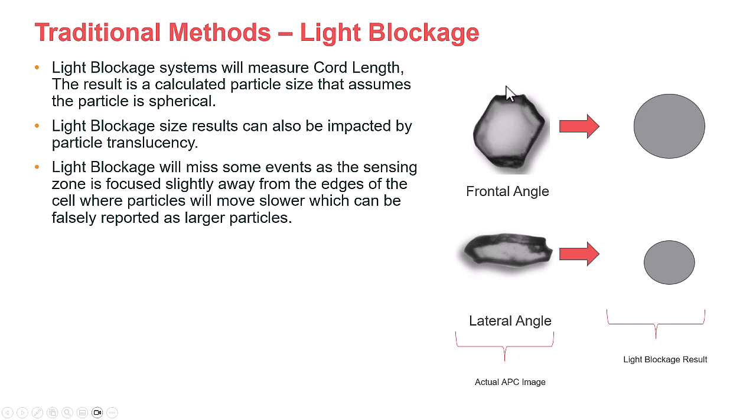So that basically means that if you have a highly translucent particle, the results that you get could actually be a bit strange, because the light can go through it. And also it can't tell the difference between bubbles and real particles. So there are a few drawbacks, but still it's a very traditional method. It's been around for a long time and it's excellent. But still, here we are because the new ISO standard is recognizing several techniques.